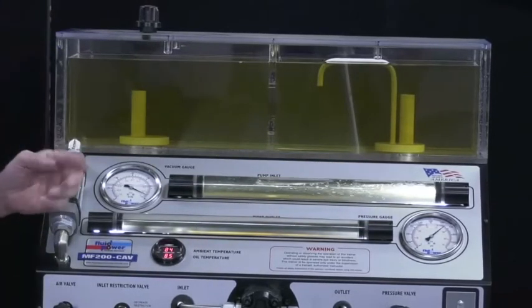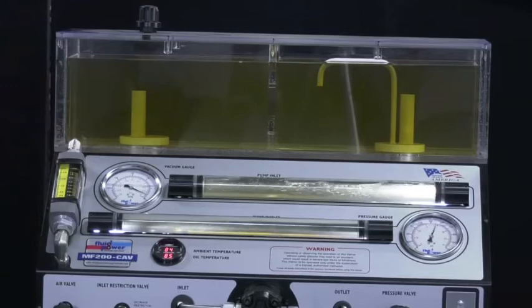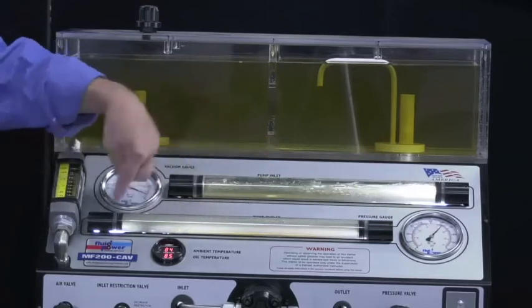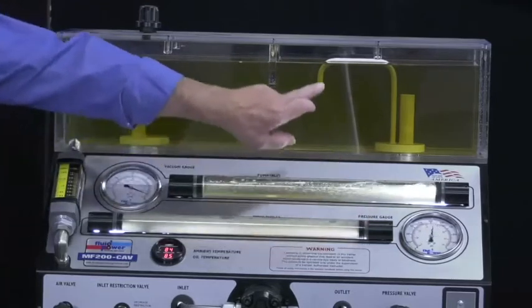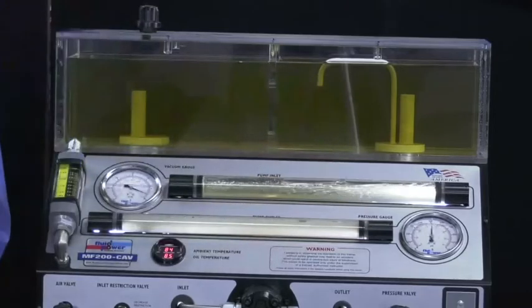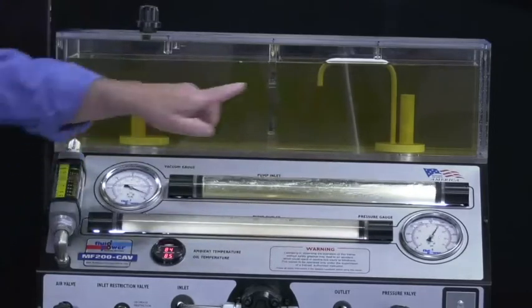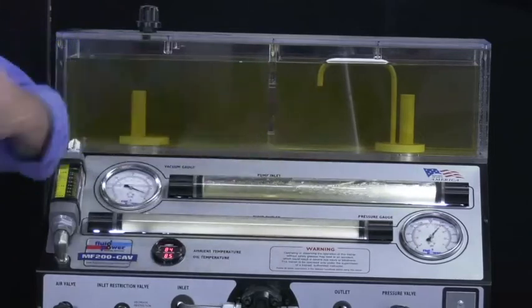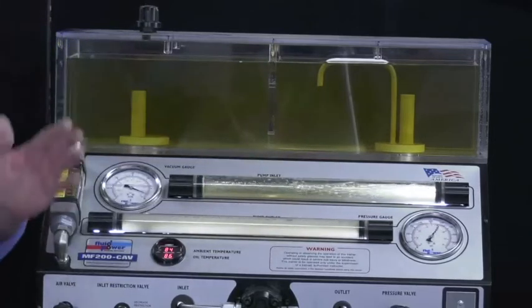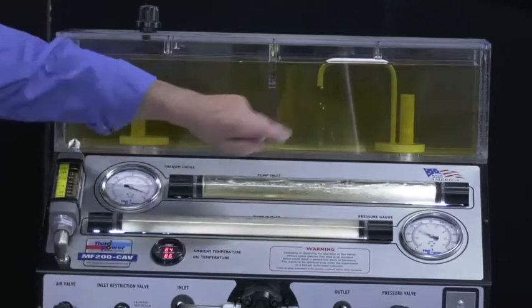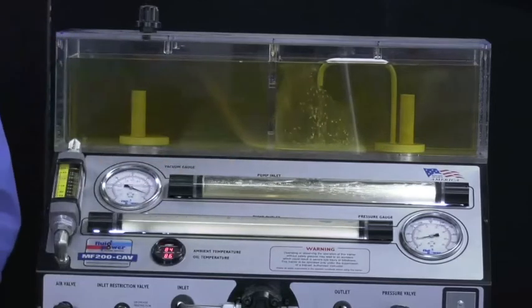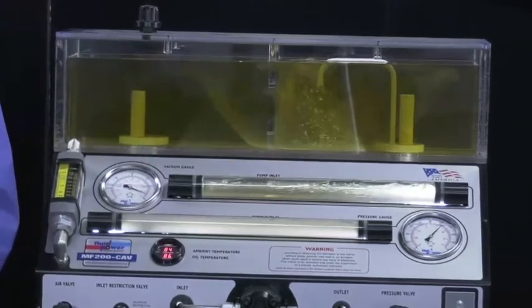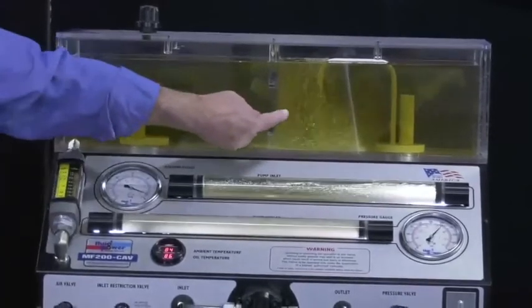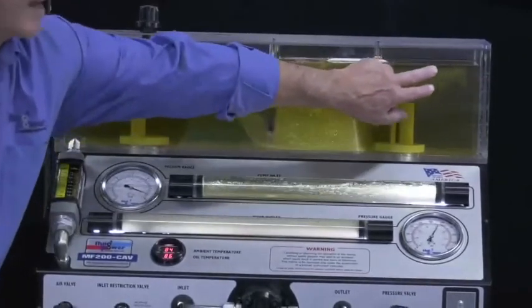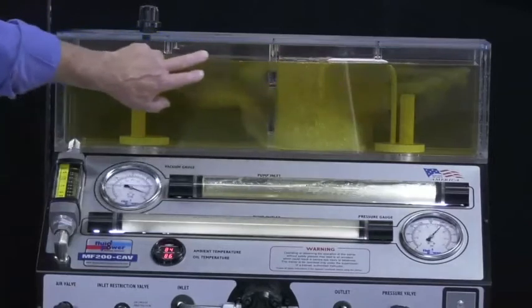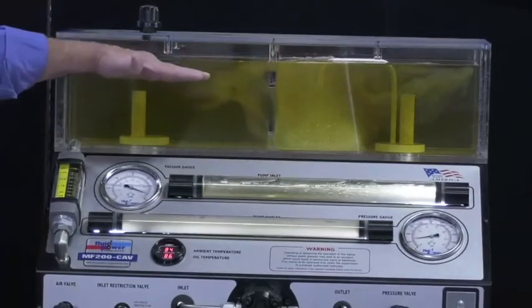Now, there it comes. I'm now going to aerate my entire hydraulic system. So the air's coming in there, it's going through the line here, and in a moment it's going to look as though the oil is actually boiling. As it comes through the return line, going through the filters, through your valves, through the whole system, it's going to look as though the oil is boiling. Notice, it's going to aerate the oil and form a cloud of air across the top. Always starts at the top and goes down.